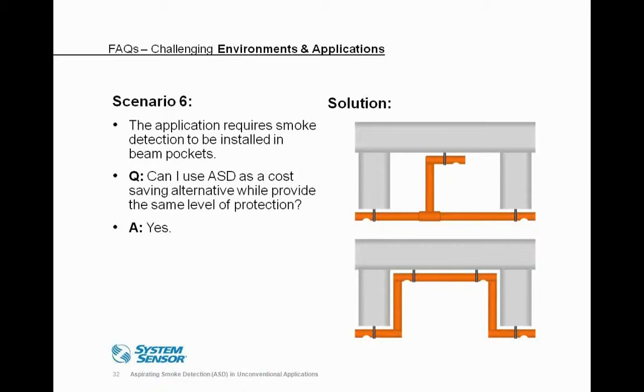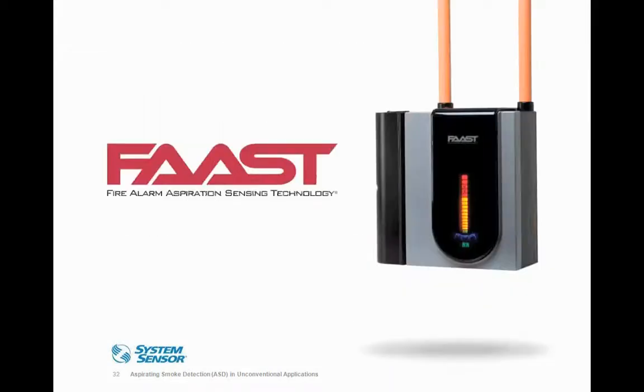Is one better than the other? Not necessarily. It all depends on the job and the installation and the size of the pipe network. When you start running into maximum pipe network designs, the one below may not be the choice because of the number of elbows needed versus the one on top. But it's site dependent or project dependent.